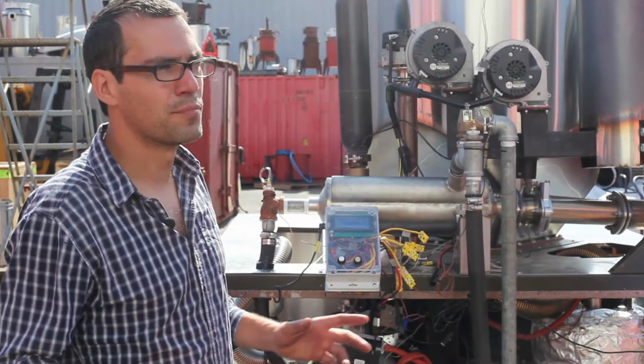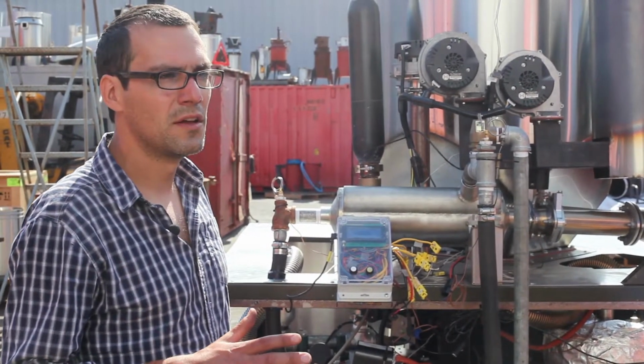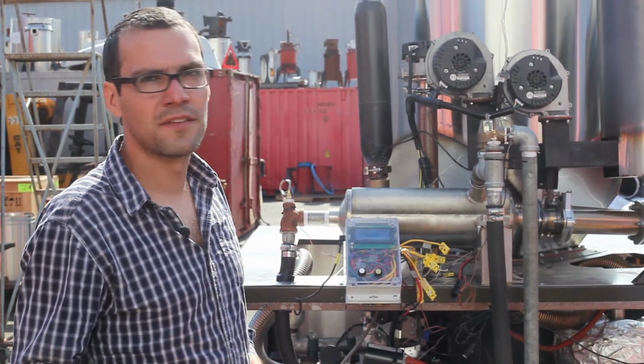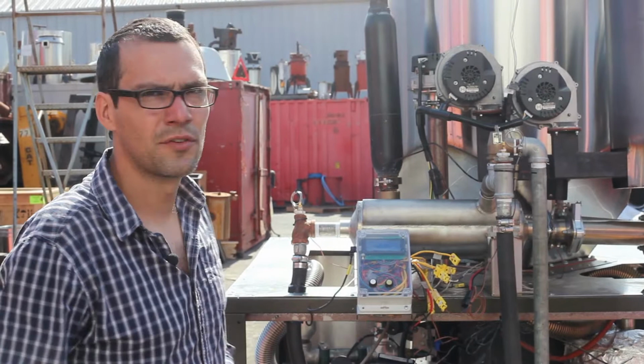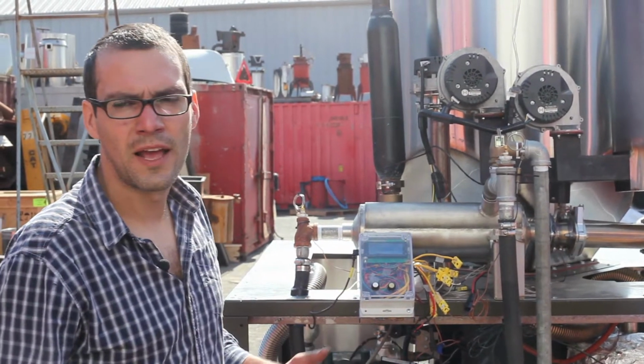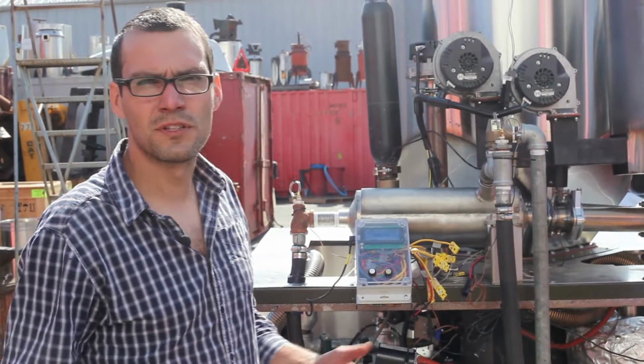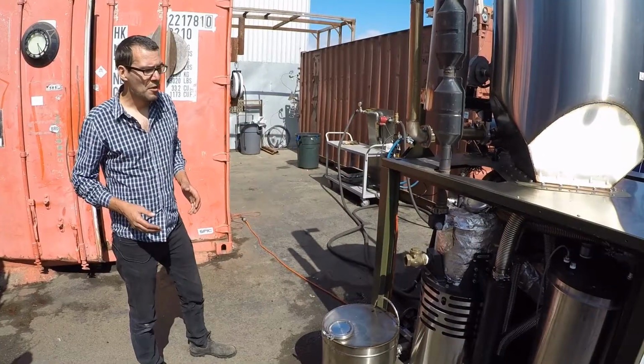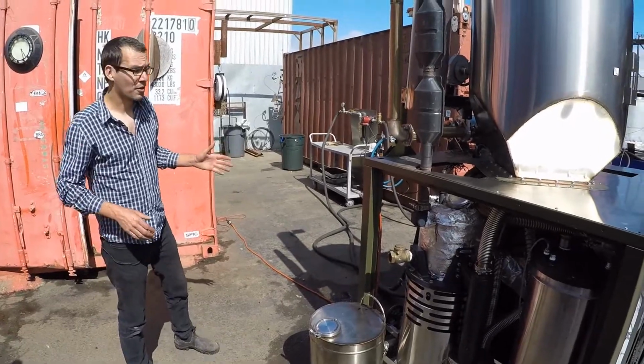This CHP system produces approximately double the amount of energy in heat to the water as it does in electrical output. So if you're running the power cube and you're generating 10 kilowatts of electricity, you'll produce approximately 20 kilowatts of heating power to the working loop. The combined heat and power system, or CHP for short, mounts on the back of our power cube.